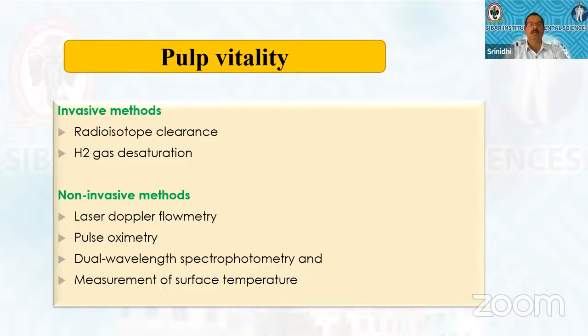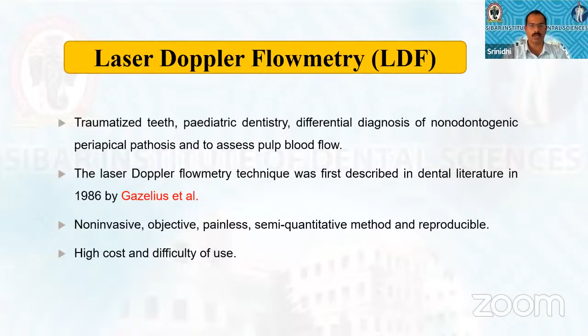It's non-invasive, semi-quantitative, and it is reproducible. So what is it actually? Light is passed through a tissue sample. If there is a moving object, that is mainly the red blood cells, the light that is passed gets frequency shifted. If a non-moving object like static tissue is there, there is no shift in the frequency. Now this will be taken by the detector which is present in the probe. So the probe is a single probe which contains both the light source as well as the detector.